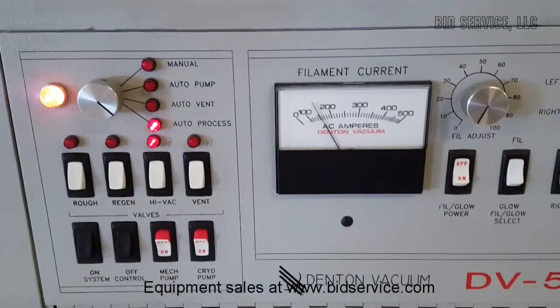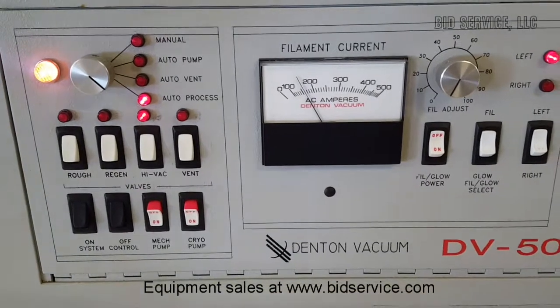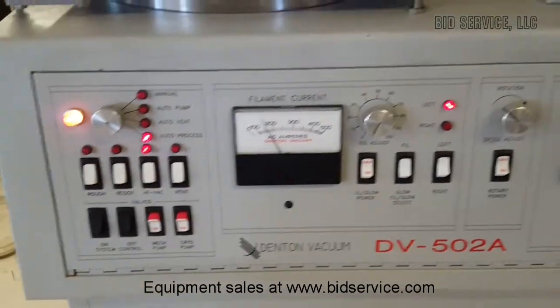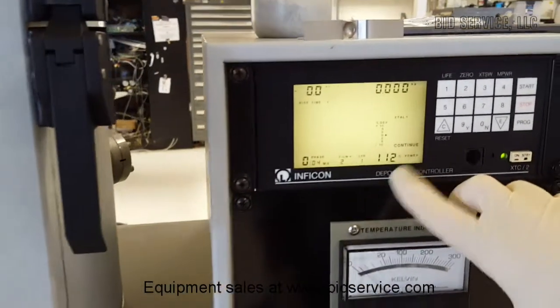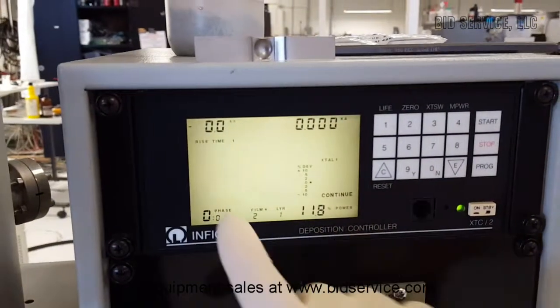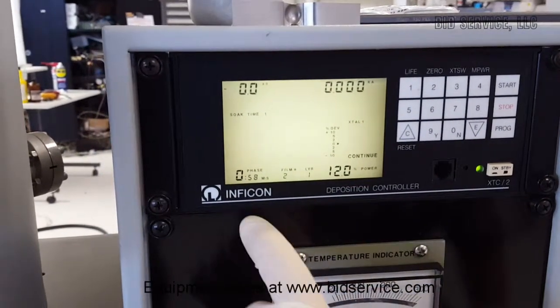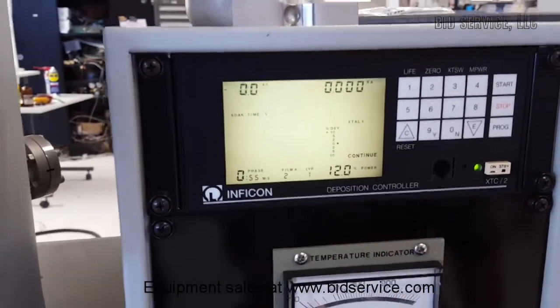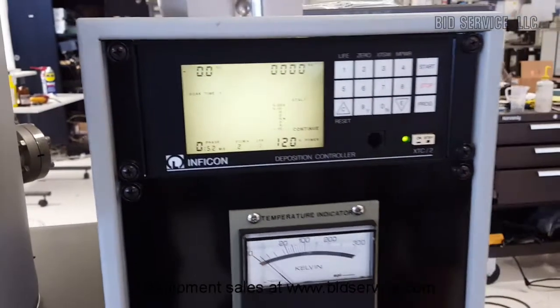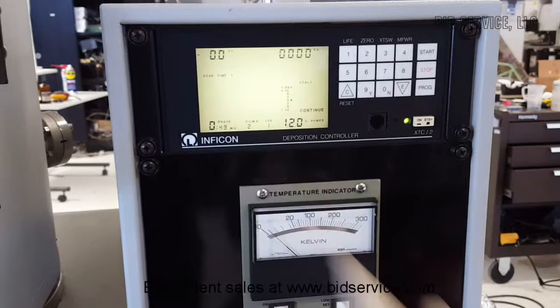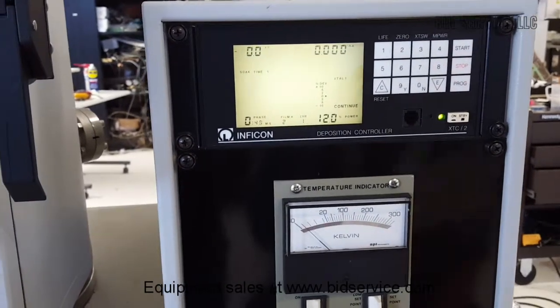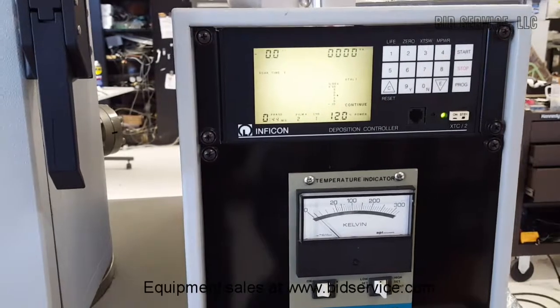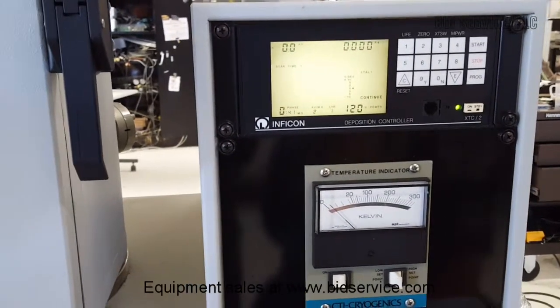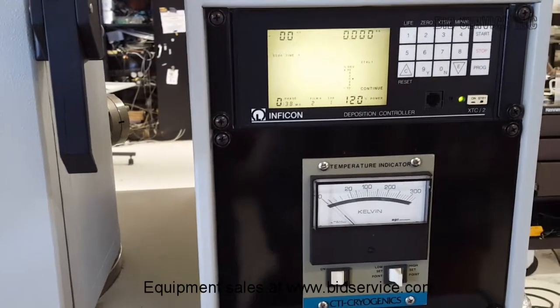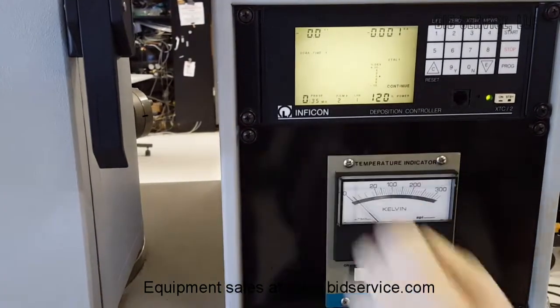So if you look over at the filament current, you can see it's now up around 150, 160 amps AC. We're getting close to the 12%. So once it hits 12%, it's going to soak there. And you'll see that this will change the soak time for a minute. Again, this is what's programmed in film number 2 that I just showed you. So we'll sit there for a minute, and then it's going to ramp up to 18%, I think it was. And it's your soak 2. We'll see that happen after a minute.